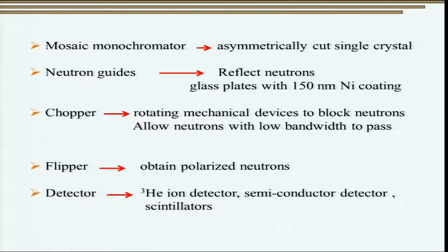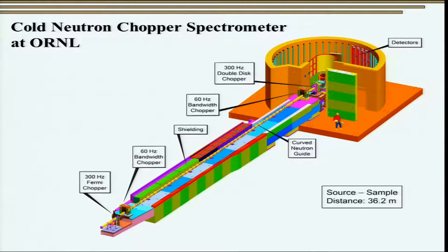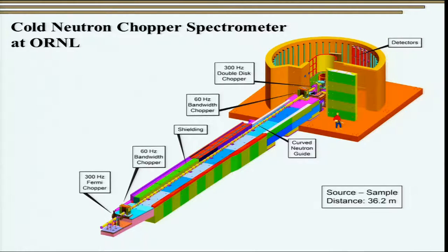The most important part of a neutron diffraction setup is the detector. The most common detector is the helium-3 ion detector, a gas-filled detector. Semiconductor detectors and scintillator detectors are also used. Shown here is a schematic of the cold neutron chopper spectrometer at Oak Ridge National Laboratory: it includes a Fermi chopper, a bandwidth chopper, shielding, neutron guides, and the sample position, with detectors arranged around it. The source-to-sample distance is as large as 36.2 meters, and everything is shielded. This instrument demonstrates why high scattering angles can be accessed using the spallation source.